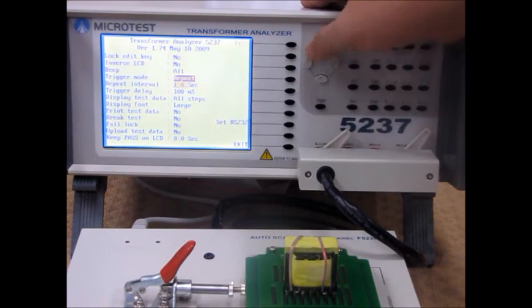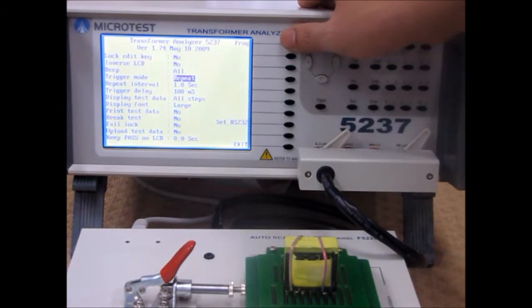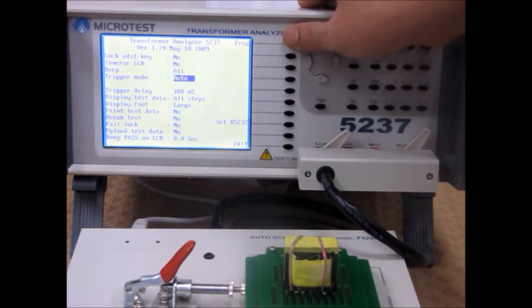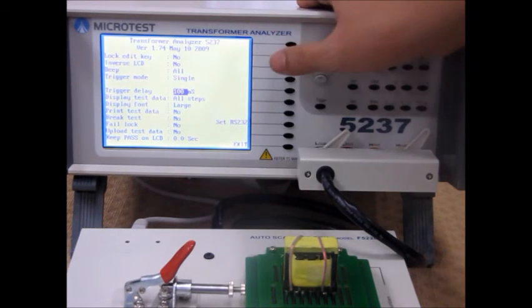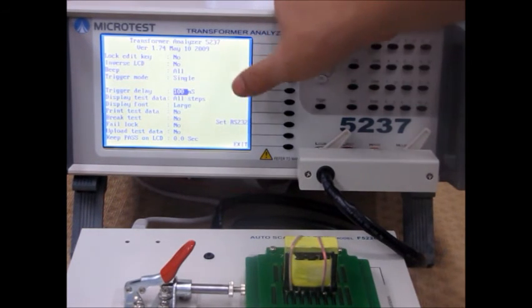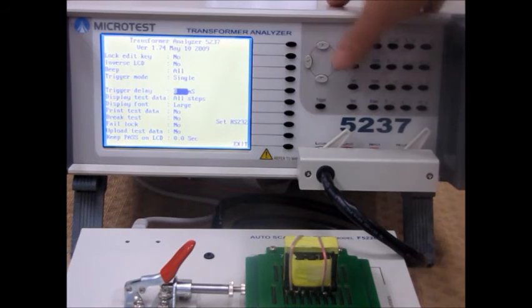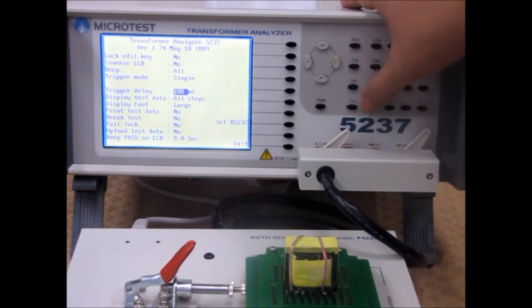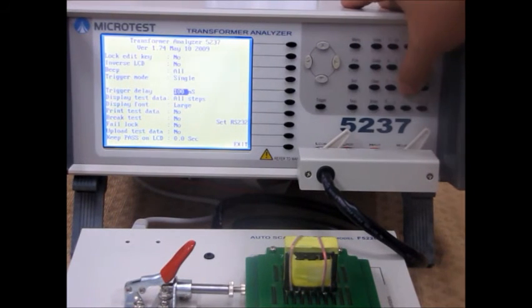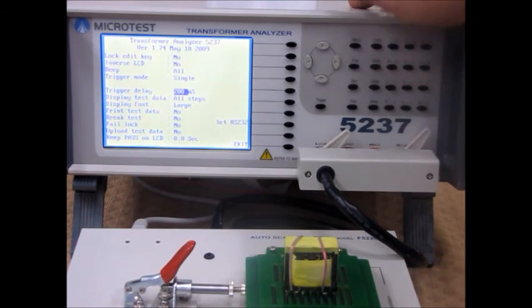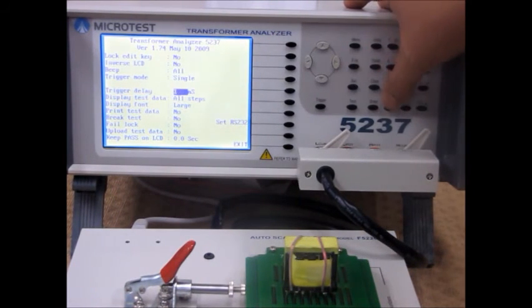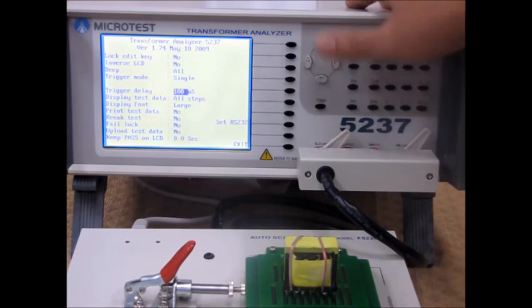Repeating means that after you press test, it will keep repeating the test in that interval. You can change the trigger delay, which means that after you press the test button, how long it will take before the machine actually does the test.